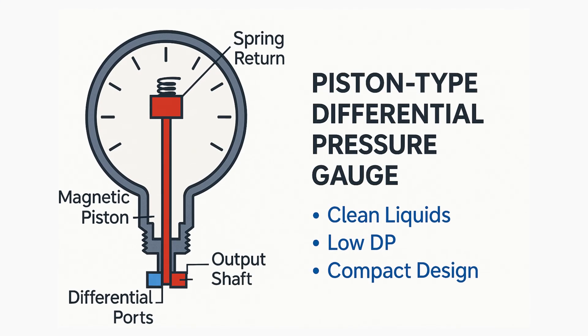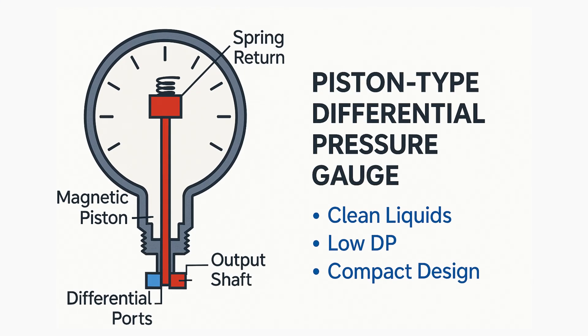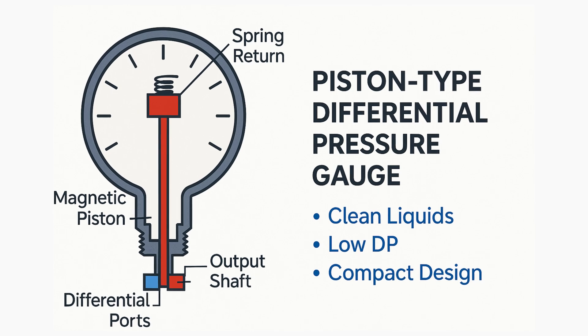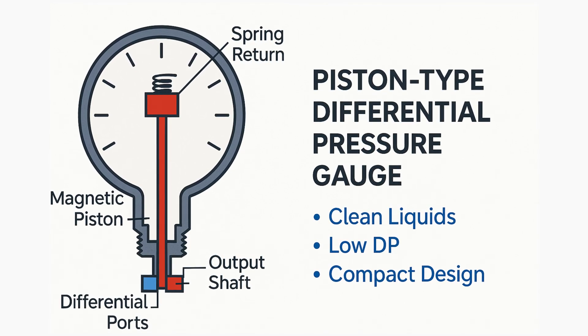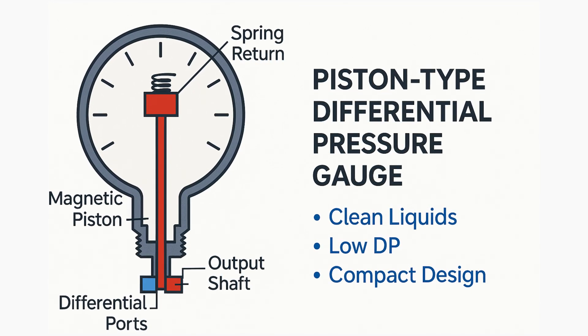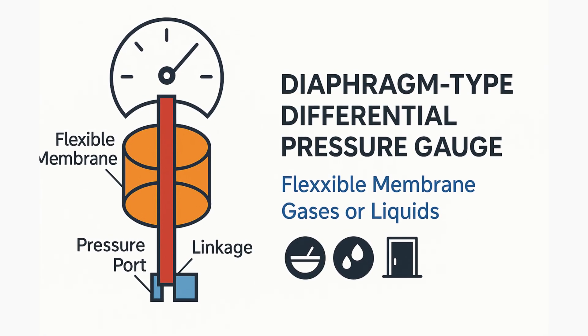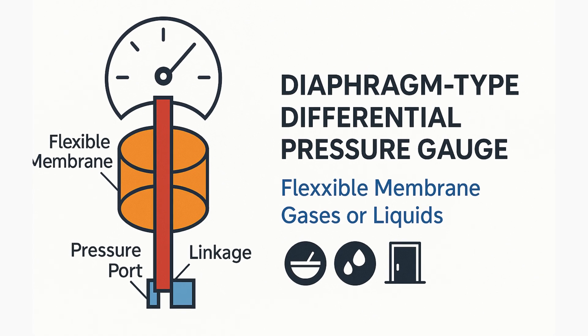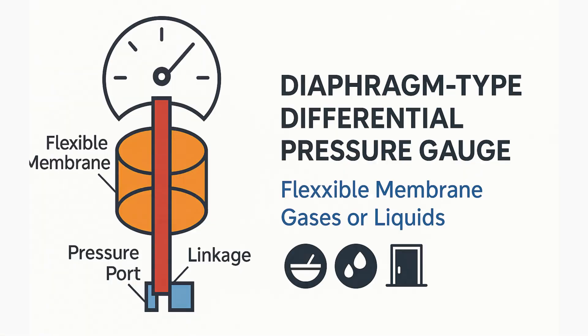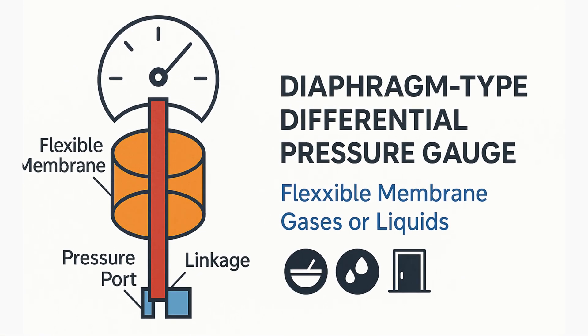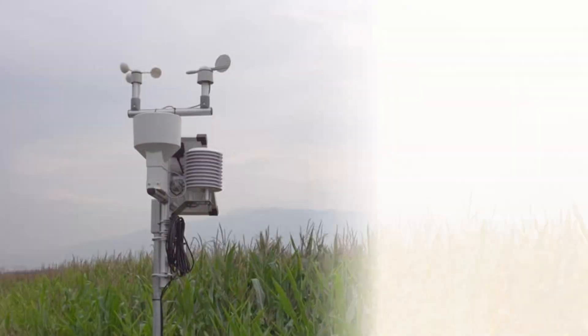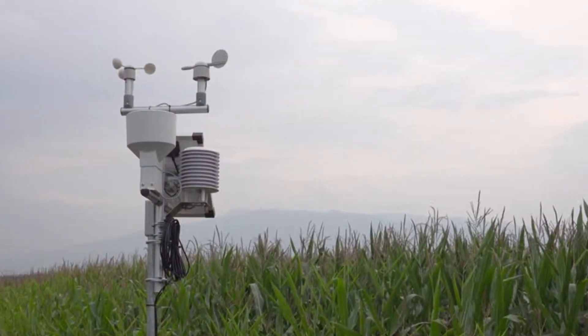Now let's cover some types of differential pressure gauges. The first is the piston type, which uses a magnetic piston mechanism and is ideal for clean liquids and low differential pressures. The second is the diaphragm type, which uses a metallic diaphragm, is suitable for gas and liquid applications, and is good for HVAC, pharma, and clean room uses.